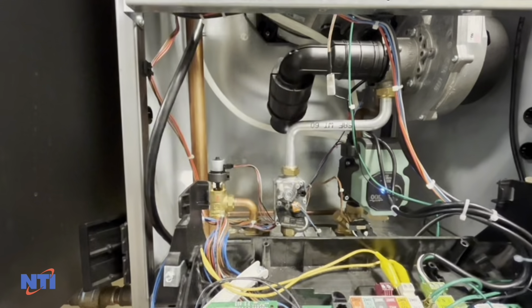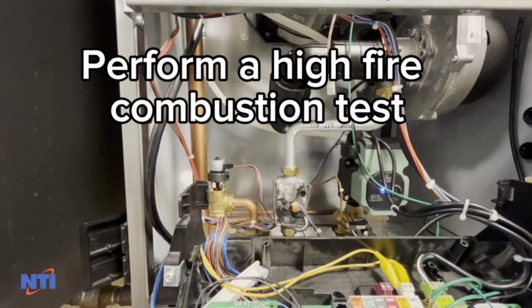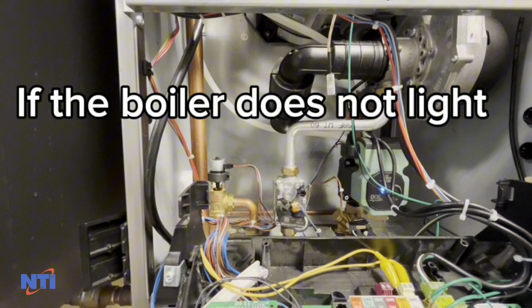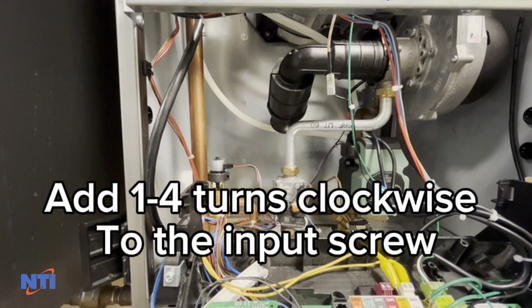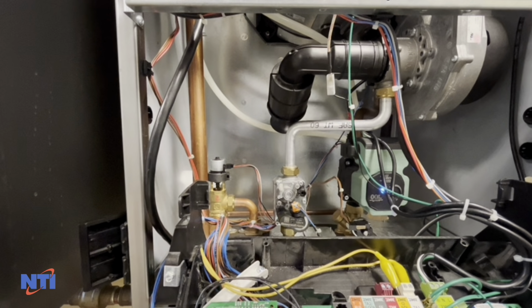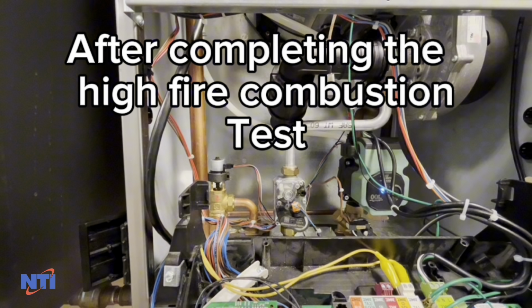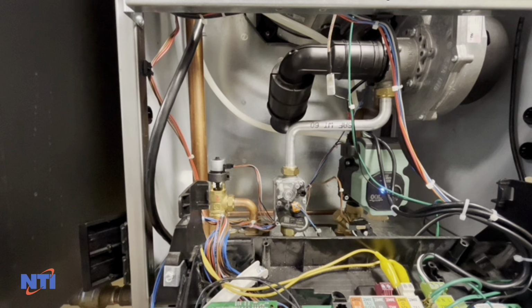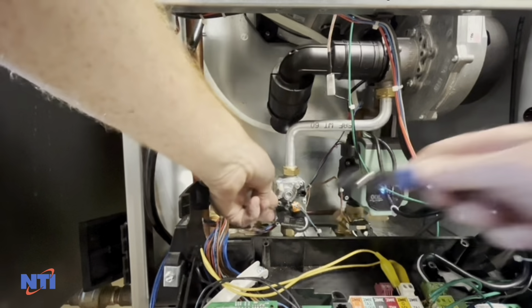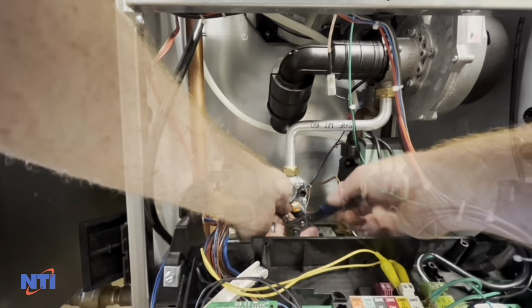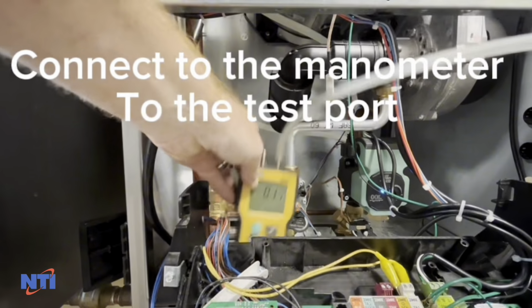Once that is complete, perform a high fire combustion test. If the burner will not light, turn the screw clockwise 1 to 4 turns to attempt to get ignition. After completing the high fire combustion test, the next step will be to do a low fire reset. Loosen the screw 2 turns over the R test port. Connect the manometer here.